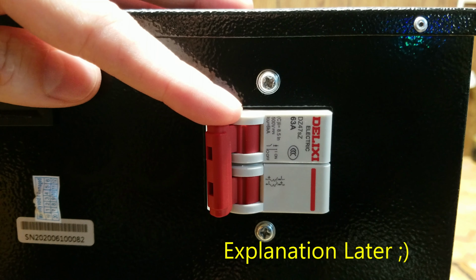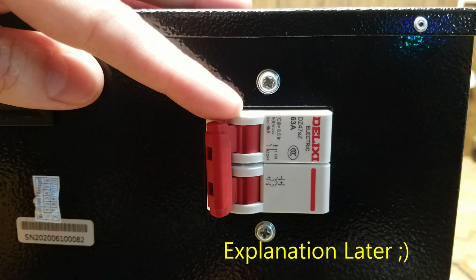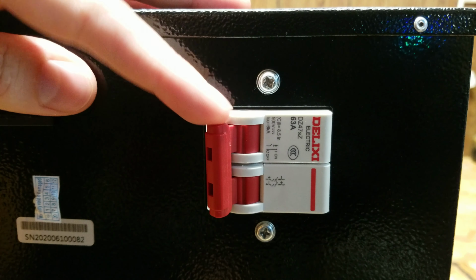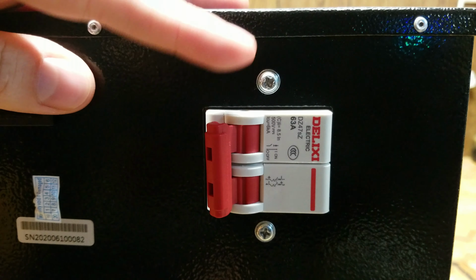So following the NEC recommendation of an 80% de-rate for a continuous load, I would not pull more than 50 amps continuous through this breaker.